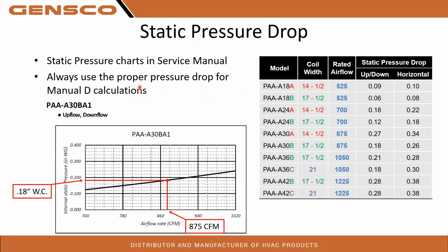Always use proper pressure drop for manual D calculations. Horizontal and upflow, downflow, all that stuff is going to change quite a bit. As you can see, as you get down here into the bigger coils, you do have quite a bit of static drop. So you want to make sure to size your ductwork and your furnace accordingly to be able to accommodate that. Refer to your installation manuals.